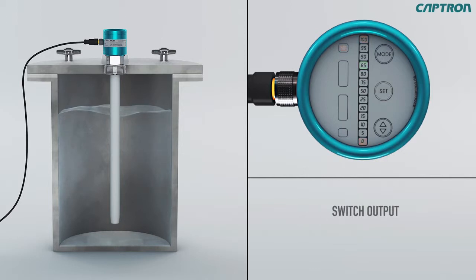To set the switch output, the 0 and 100% displays will light up once again, as well as the NO or NC display. NO stands for normally open, and NC for normally closed contact. You can set NO or NC with the up-down button. With set, you confirm your adjustment. The probe then jumps to the next step, setting the switch point.